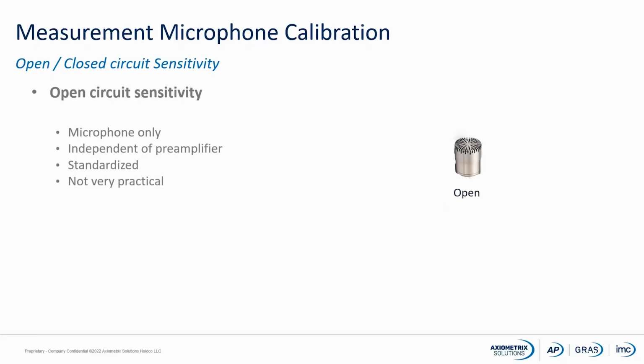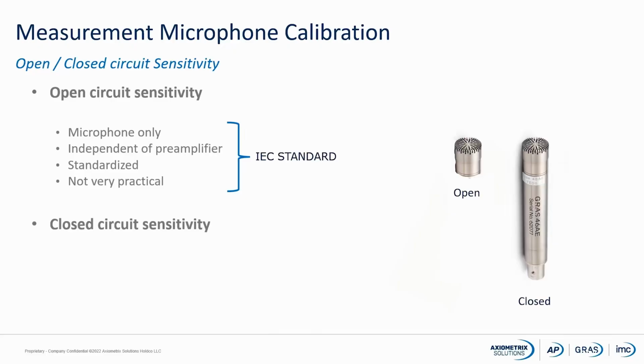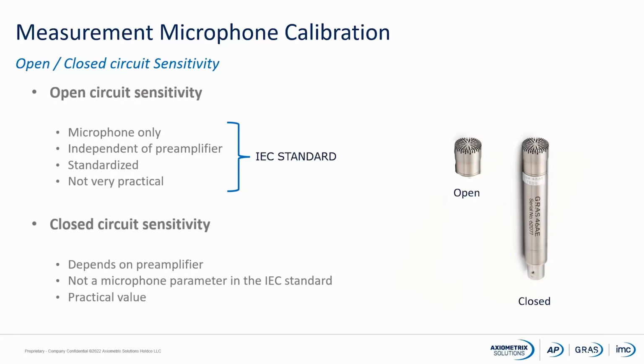Open circuit sensitivity, we talked about it before. It's only for the microphone. It's independent of the preamplifier. It's a standardized value, but it's not a practical value because all of you will use a microphone together with a preamplifier. So therefore, from day to day, you are using the closed circuit sensitivity, which of course depends on the preamplifier. And it is not a microphone parameter according to the IEC standard. But it is a very, very practical value because it's a value you can put into your analyzer, so you are ensured that you are measuring correctly.